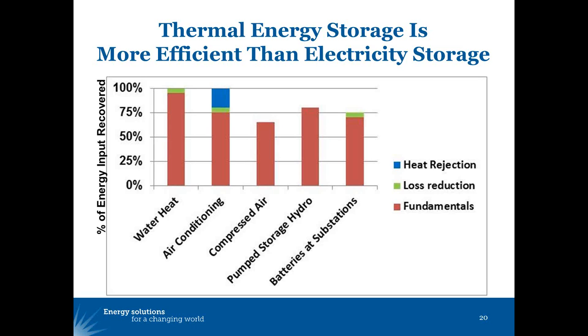And if you can then fill that air conditioner with ice in the middle of the night when the grid is coasting, you might have marginal losses of 5 or 6 or 7%, and you can wind up with about 15% avoidance of losses just by shifting from night to day.